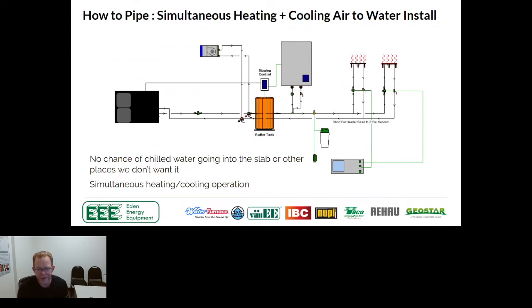So in this case, and this is actually one of my more preferred ways, I'm using Belimo 3-way valves to divert before the buffer tank. So the idea here is that my radiant floor loads is where my modulation is going to happen. I've got actuators on it, so I could have microzones. The cooling's a fixed load. And these heat pumps, these 3 that I showed you, are all modulating. So they can compensate up and down to a point. I really don't need it for the cooling application. So the nice part for this is that I can bypass for the cooling.